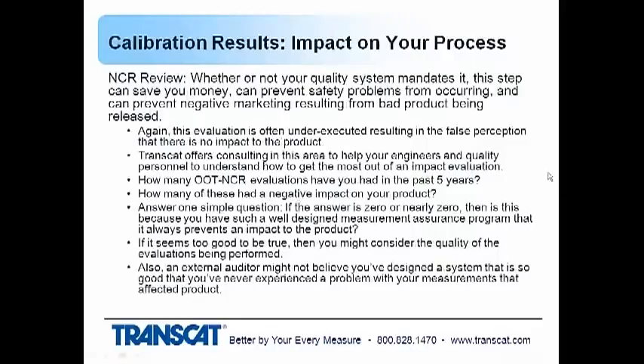So let's talk about the end result. Assuming that the calibration is performed correctly, the tolerances are right, all the test points are there that you need, and a good technician performs the calibration, competent for the measurements. Now you get to evaluating the out-of-tolerance results and performing a nonconformance review. Whether or not your quality system mandates that you do this, doing so can help prevent safety issues, can save you money and costs, and can prevent negative marketing of your product if you're getting bad results.